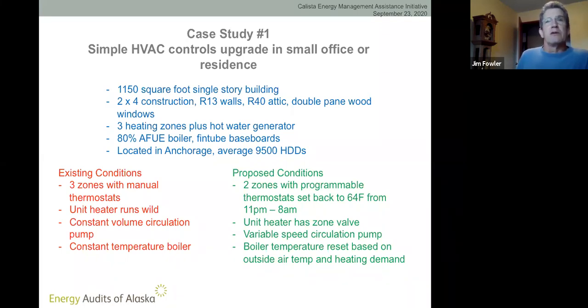The proposed conditions, or the upgrade, is to put programmable thermostats on 2 of those zones and set back the temperatures from 11 p.m. till 8 a.m. to 64 degrees. Put a zone valve on the unit heater so that the fluid is not flowing through there all the time. Put in what's called a variable speed circulation pump so that when there's a call for heat, if it's a small call, the pump turns on very slowly. If it's a larger call, then the pump pumps fully. And then reset the boiler temperature based on the outside air. When it's really cold outside, you need a hotter boiler. When it's not very cold outside, you can turn the boiler temperature down. And then the other reset would be based on how much call for heat there is.